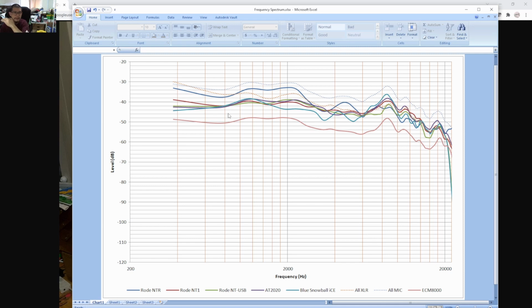This is meant to be a calibration microphone. It's meant to be flat across the normal hearing range and only towards the higher frequency range does it do a little bit differently. And what we can see here is the shape is actually very consistent, very similar to the blue one, this nice dark blue one, which is the ribbon microphone, which at the time I believed to be closest to a flat response. As we run up the frequency past 2000 into 3000, you once again see a little bit of a drop off, very similar, but unlike the ribbon microphone where you have the secondary hump, it continues to fall off, and then you get into some of this strange squiggle stuff over in the 8000 plus range, which, from discussions I've had with somebody who actually works in audiology, over 8000 hertz is really quite insignificant for most people.